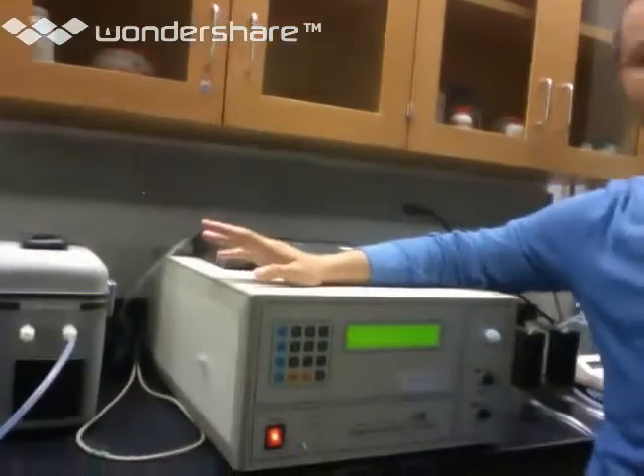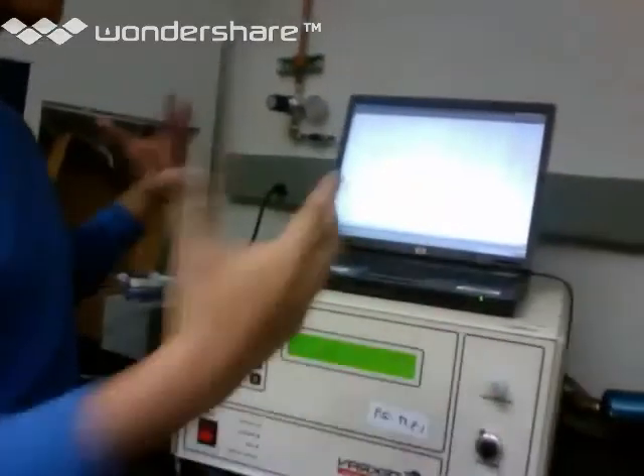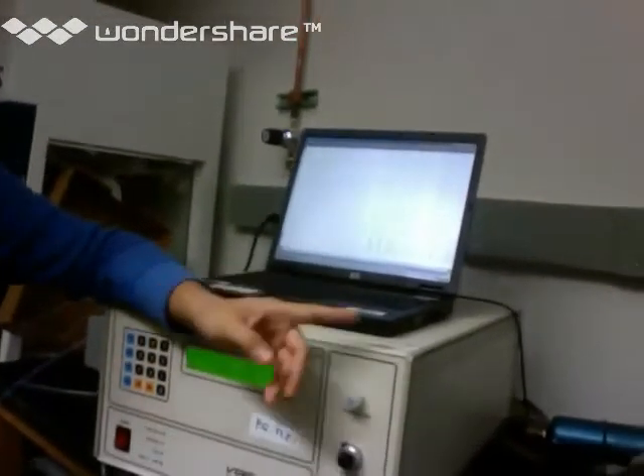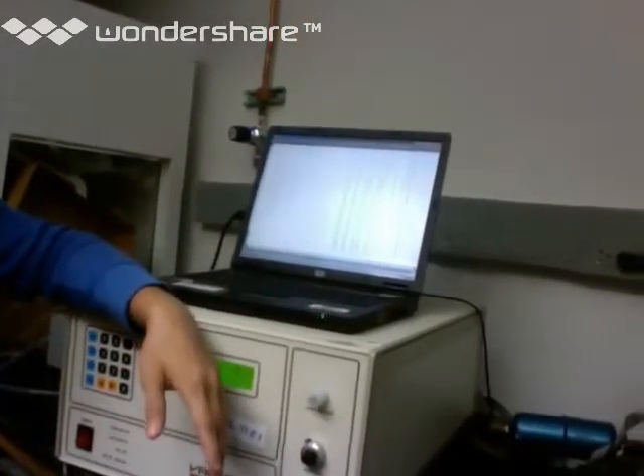I turned the zero air on because we've been having issues with our cables. There is an actual communication cable between the Tekran, the port sampler, as well as the zero air. However, I just don't want to run the risk right now because I ordered a couple new cables for this. They're ribbon cables. They're this thing, if you see. This cable here connects actually to the Tekran and the port sampler. That's how the Tekran tells each unit to feed it whatever air. Does that make sense? And so, if you have that ribbon connection, you don't need the zero air. You do need the zero air, but you don't need to turn it on. Okay. Okay. It'll go auto.